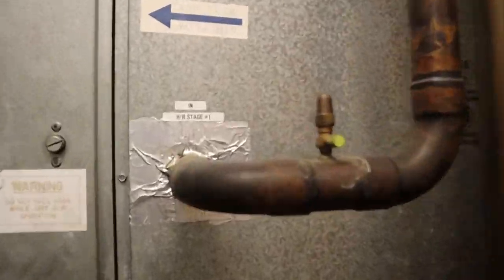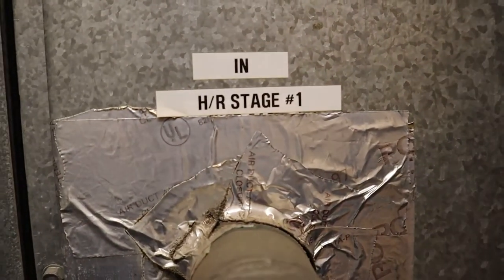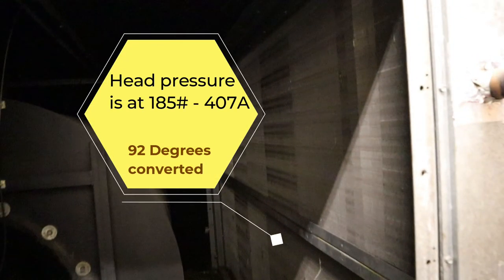Going to the air handler room — heat reclaim stage number one coming in. Here I'm showing you the heat reclaim coil: top is stage one, bottom is stage number two. You can see the size of it. Right now our head pressure is 185 pounds at R-407A gas, so it converts to 92 degrees — that's how much heat we're getting from it.